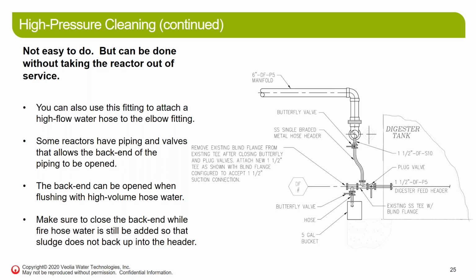So we have piping and valves that allow the back end to be open. Just further down, not shown on the drawing, you would have a valve on the other side of the tank. Say it's a 6-inch on this side, it might be a 3-inch on the back side, and the pipe goes all the way through. If it's completely clogged, you can open it on the one end, connect a power washer, and open the back end and just push it through. Or you could just hook a hose up and flush a high volume of water through there.